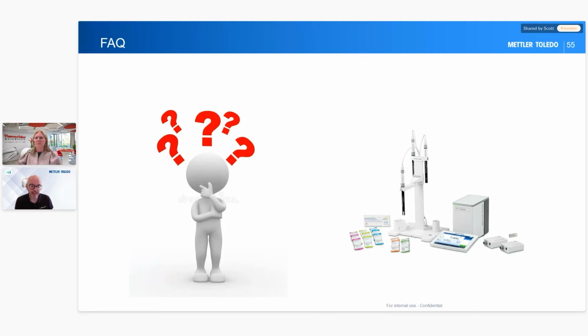Yes. Again, we have a range of different electrodes. I think there's over 90 different Mettler pH electrodes in the range, so you can go and take a look. One of them is what we call a Solids Pro, or a Solids Pro ISM. This is a puncture electrode, so it's a glass electrode, it's gel filled, and it has a little tip, not sharp, but almost like a conical tip, and that is for puncturing meat, cheese, solid samples, and semi-solid samples like agar, for example. You could use them in solid samples as long as the solid is a moist sample to take a measurement.